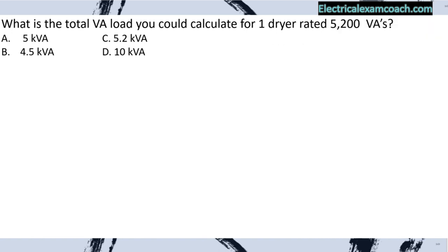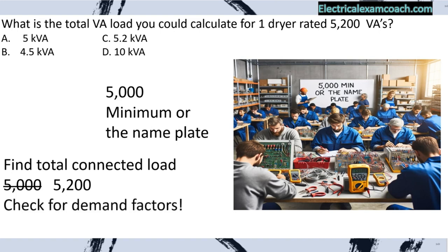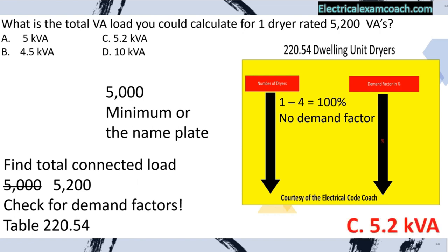Practice problem: What is the total VA load for one dryer rated at 5,200 VAs? Find the total connected load: 5,000 minimum or the nameplate, whichever is larger — in this case the nameplate is larger, so we select 5,200. Check for demand factors: per Table 220.54, one to four dryers is calculated at 100% — no demand factor. We select C.